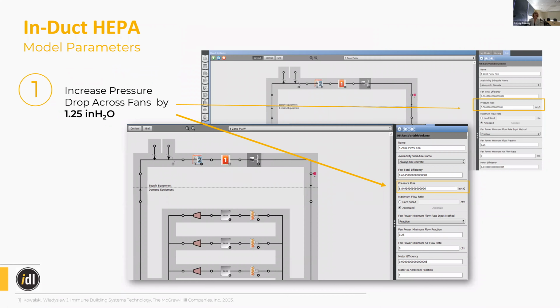So in-duct HEPA filters, instead of your portable plug-and-play option. You can also have a HEPA filter, which just means, again, 99 or 98% filter efficiency. You can put it in your duct, in your air handling unit, just like a MERV filter, but there's going to be a much higher pressure drop associated with that. If you remember the MERV filters, we modeled a pressure rise of 0.4 inches of water gauge. With the HEPA filters, our research indicated we had to up it to 1.25 inches of water gauge. So quite a bit different.